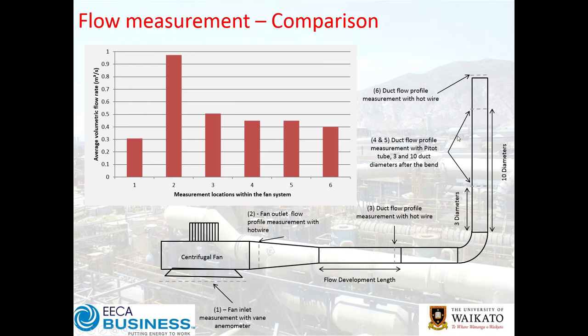Comparing measurements using a vane anemometer, a hot wire anemometer, and pitot tubes, you'll notice one measurement is undershooting the flow rate. Measurements 3, 4, and 5 are fairly representative; measurement 6 is a little low because it's hard to capture all the flow at an open exit — better to come back from the exit for a good result. The flow rate is probably sitting around 0.45 in reality. Why does one undershoot? Measuring at the open contraction into the fan inlet makes it hard to fully capture the flow.